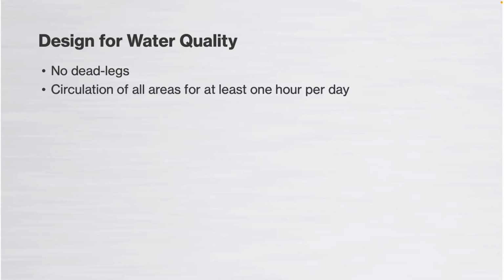We want to avoid dead legs, stagnation. Consider stagnation a bit of a killer, to be dramatic, but to drive the message home. Stagnation and dead legs are really not a good place, or don't have a place on a closed loop system. So thinking about that design when a control valve operates, or in terms of controls philosophy, we need to ensure that we keep water moving, essentially. So minimum 1 hour every 24 hours. You want all that water moving and actuating valves and so on.